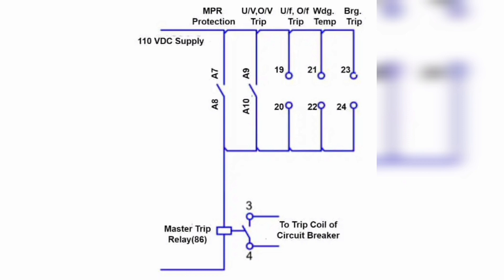Heavy Trip 86H: If the magnitude of the fault is very high, it may damage both electrical and mechanical equipment. The Heavy Trip Relay 86H output is wired with turbine tripping, grid breaker tripping, and generator breaker tripping. The Heavy Trip Relay, also called the Lockout Relay, issues a trip command to the grid breaker, generator breaker, and turbine. When the protection relays sense the following faults, the 86H relay outputs a trip command.